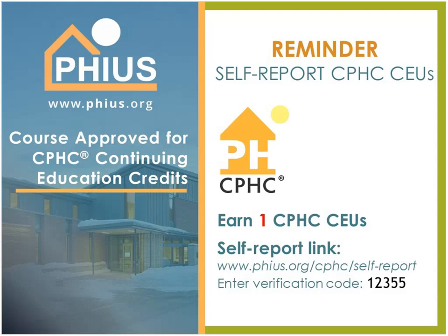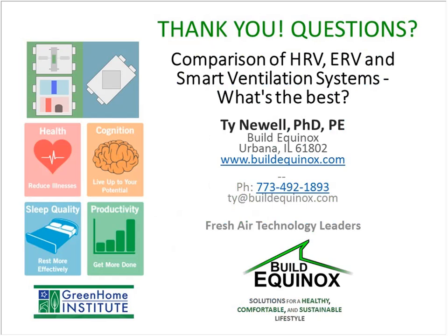Great, thanks. I was looking at this question here from Mark on mentioning the smart ventilator in the winter lets moisture freeze. What do you do to deal with ice in that regard? Oh, okay. Yeah, I didn't get to that one or see that one, but we have a defrost algorithm within it. It's one that makes use of the heat pump. It's not an electric resistance, but similar to, say, a mini split going into defrost mode, these cold temperature mini splits, and so we're able to defrost as needed.